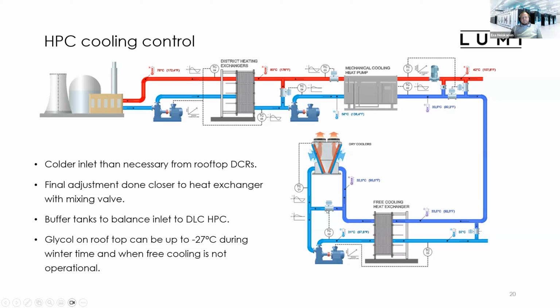And this helps us to make the adjustment quicker than running all this liquid flow through the rooftop and through the heat exchangers. So operating closer to the heat exchangers, it's much faster to do the cooling operations. So this final adjustment is done with this mixing valve close to the cooling heat exchanger. And we also have these buffer tanks in place, which balance inlet directly to the HPC cabinet CDUs. And this has been pretty good investment. And as I previously told, this glycol on the rooftop can be down to -27 degrees during the winter time, when free cooling is not operational and we are completely operating with the heat pumps.